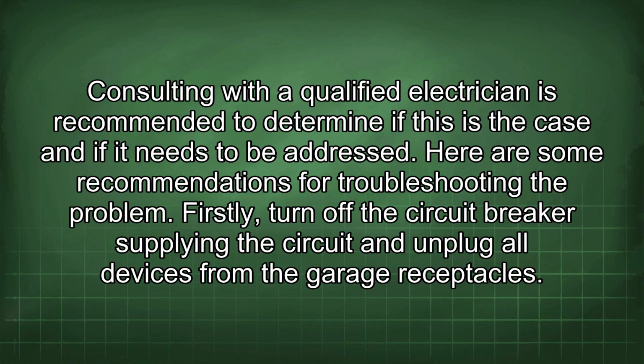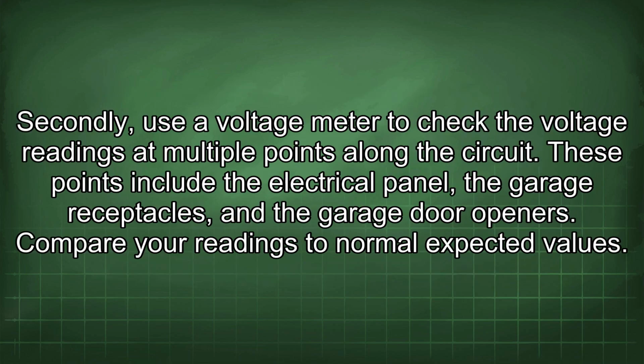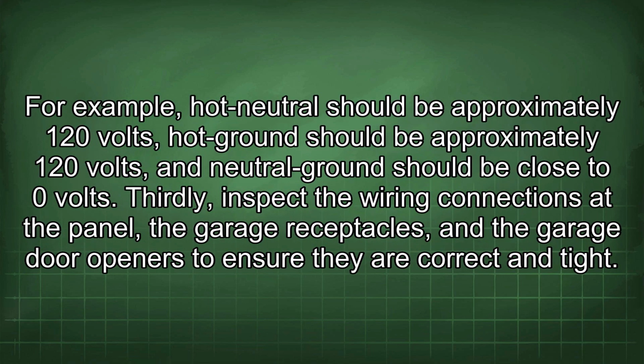Firstly, turn off the circuit breaker supplying the circuit and unplug all devices from the garage receptacles. Secondly, use a voltage meter to check the voltage readings at multiple points along the circuit. These points include the electrical panel, the garage receptacles, and the garage door openers. Compare your readings to normal expected values. For example, hot neutral should be approximately 120 volts, hot ground should be approximately 120 volts, and neutral ground should be close to 0 volts.